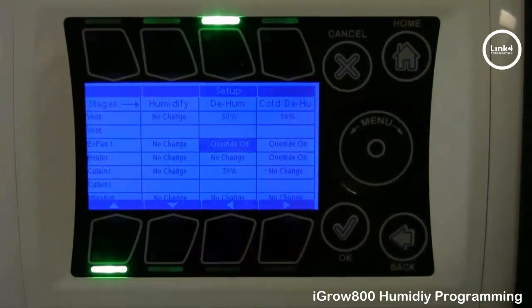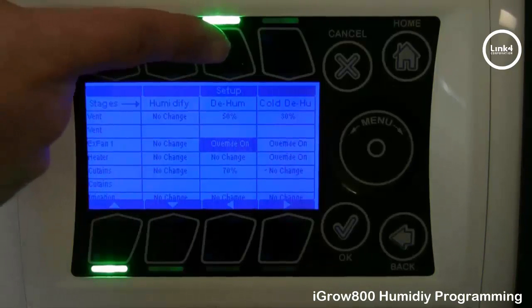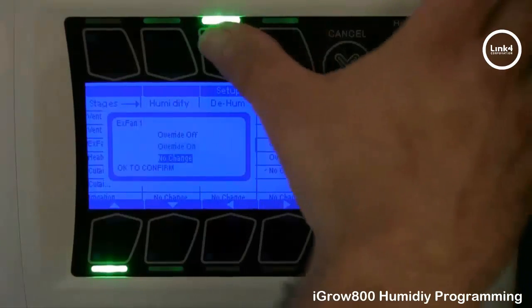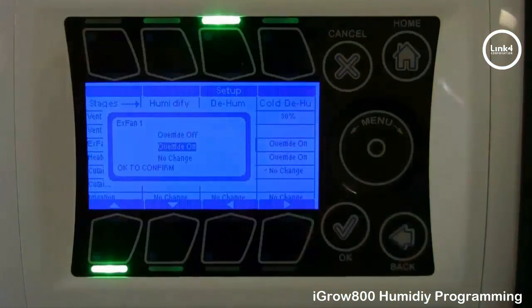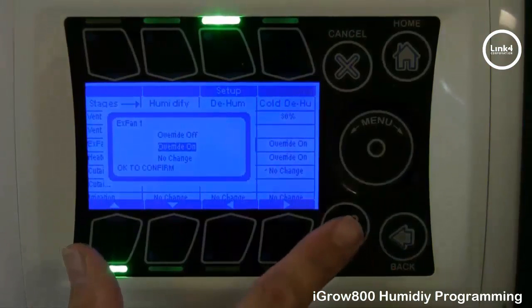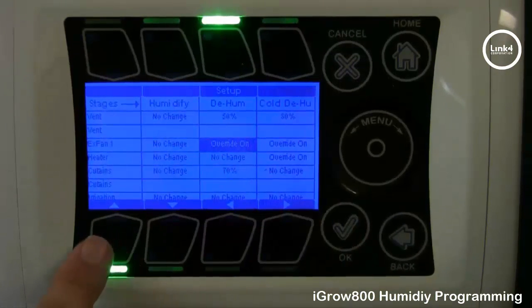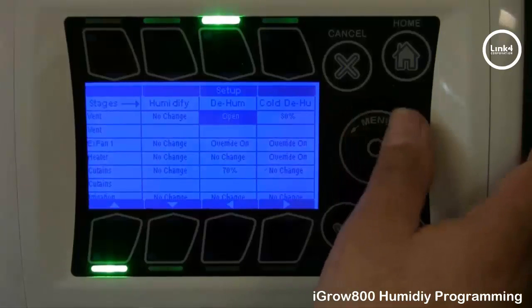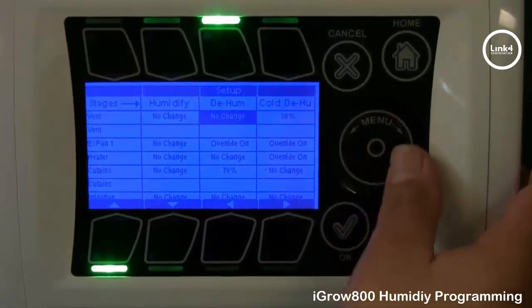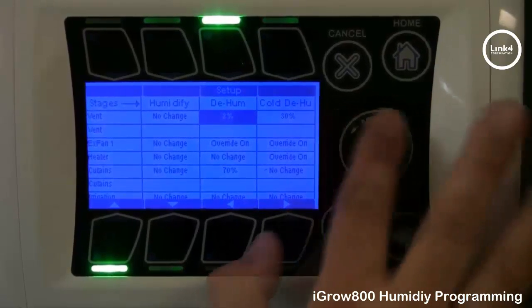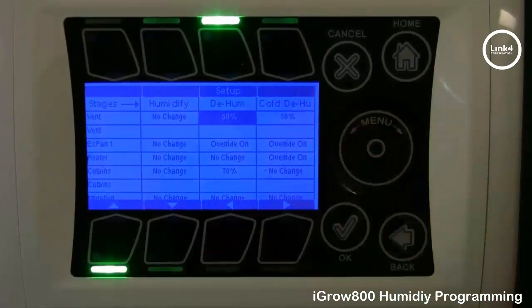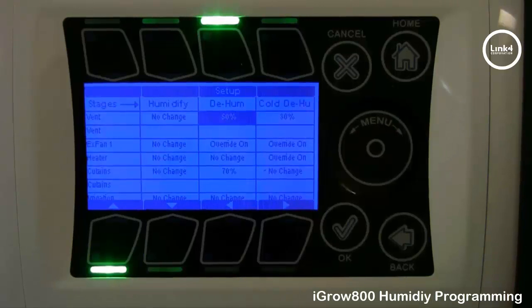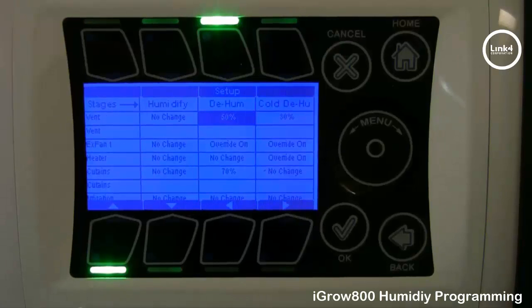Navigate your cursor to the location you would like to change. To change the state of equipment, simply hit the setup button, which gives you three options: you can override it on, no change, or override it off. For this example, we're going to have our fans override on in dehumidification. For vents and curtains, you can input a percentage for it to open — open all the way at 100%, no change, or close. For our example, we'll leave it at 50%. For vents, zero indicates fully closed and 99% is fully open. For curtains, 0% means the curtain is uncovered and 99% means the curtains are fully covered.